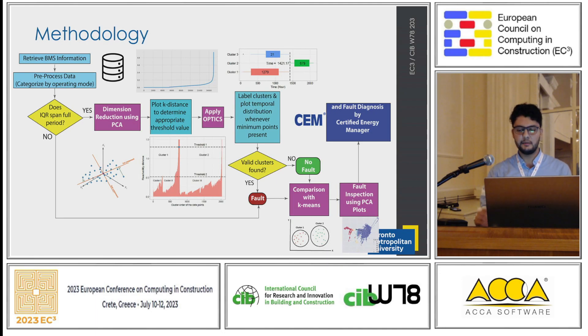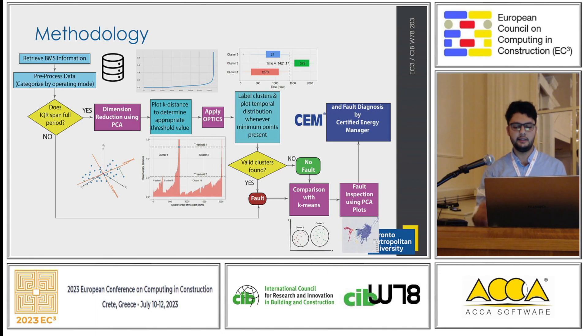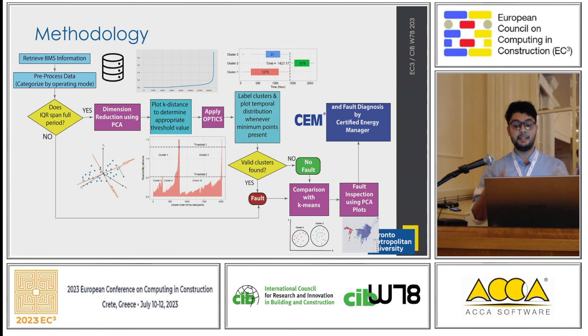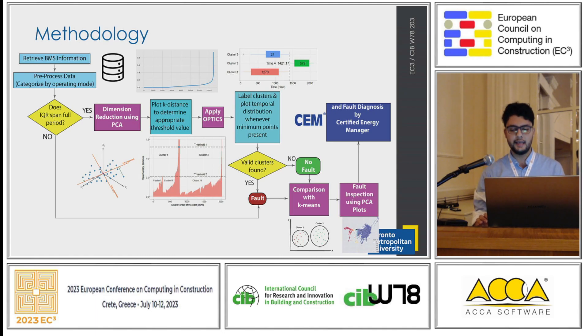We see the proposed fault detection strategy for FCUs in this figure. It mainly consists of three steps: data preprocessing, data clustering, and result evaluation. The idea is that faulty data and normal data have different characteristics, so faulty data will be spatially and temporally separated from the normal data. The separation between faulty and normal data is detected using cluster analysis.